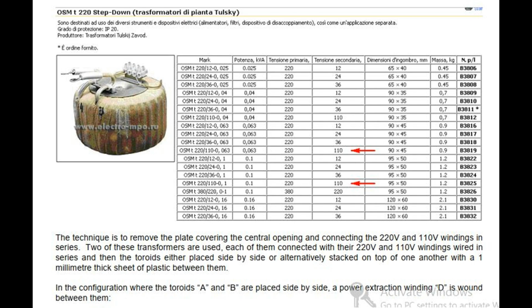The technique is to remove the plate covering the central opening and connect the 220 volt and 110 volt windings in series. Two of these transformers are used, each with their 220 volt and 110 volt windings wired in series, and then the toroids are either placed side by side or alternatively stacked on top of one another with a 1 mm thick sheet of plastic between them.